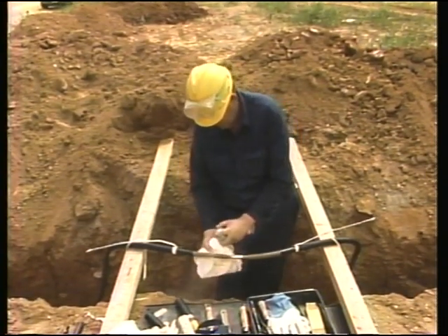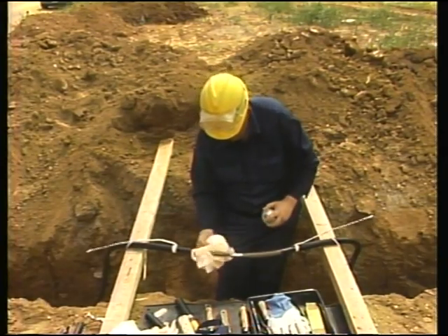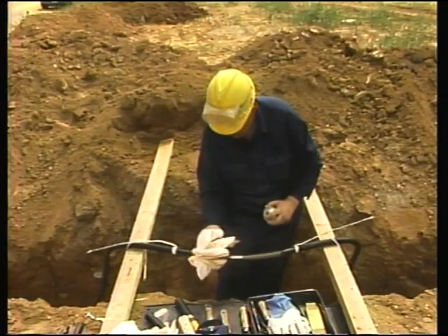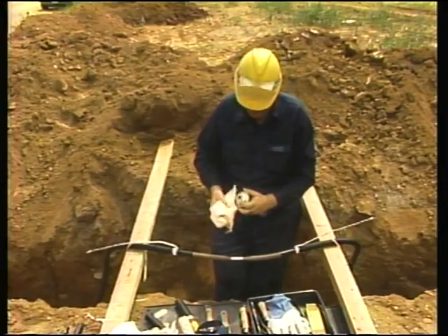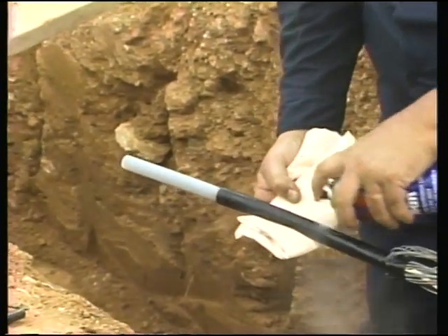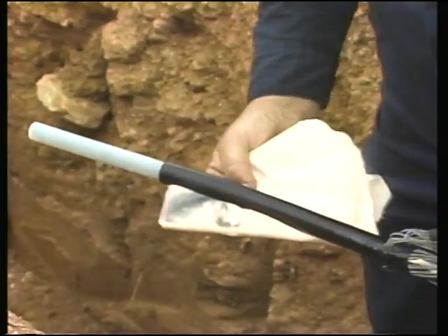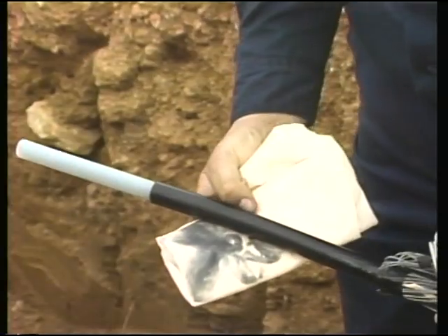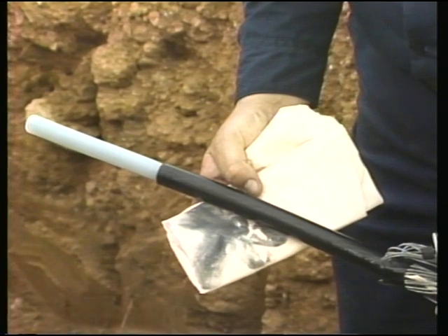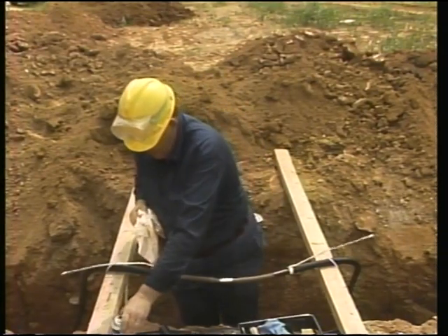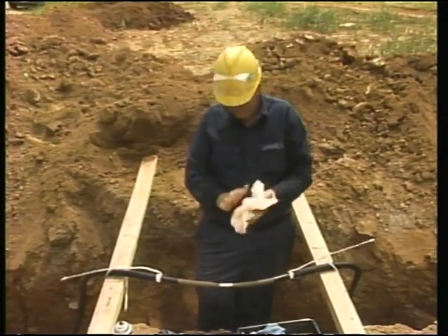Using solvents and an approved cloth, the cable insulation is then cleaned. This is done to ensure that the splice is clean, because contaminants could supply a conductive path between the conductor and the insulation shield layers. Because the solvent can dissolve the semiconductive layer, when you're cleaning the cables, be sure not to re-clean the cable insulation with a contaminated rag. Doing this could create a conductive path. The workman then wipes his hands to rid them of any conductive contaminants before beginning the tape application.